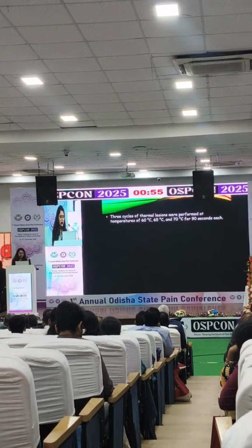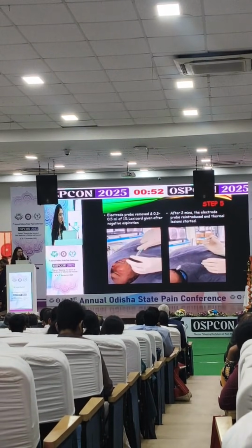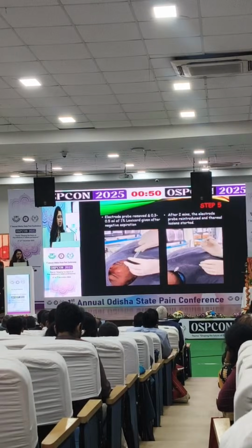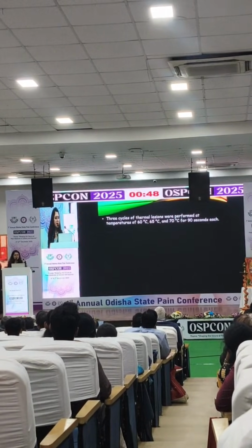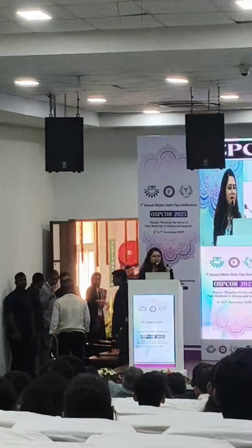So this is the electrode probe. I just want to show you in this photo if it's clear. This will be introduced inside the cannula. So 3 cycles, usually we do 3, sometimes 4 can also be done. Thermal lesions are performed at temperatures of 60, 65 and 70 degrees. Some people go up to 75 but it's not recommended, for 90 seconds each. So this is a video where you can see, just take 1 minute.